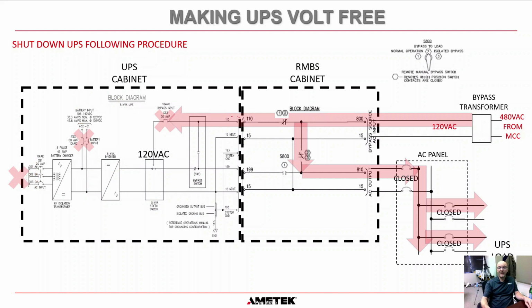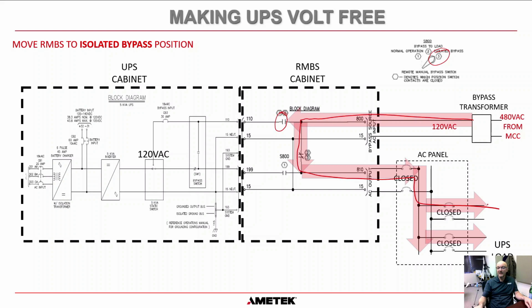But we still have power on this contact here and we need to remove that. The way to do that is to go to position 3 that you can see at the top right hand corner here. What that did was open this contact here. So we still have power flowing through this contact out to the load circuits. But now this contact is open, this contact is open. We have no power on these terminals, no power on these terminals, no power on these terminals, and no power on these terminals.